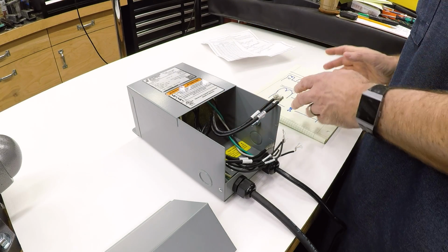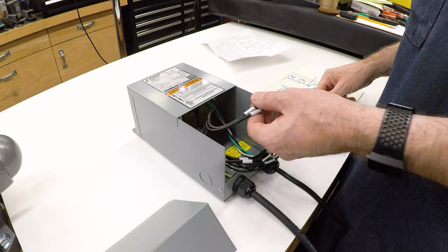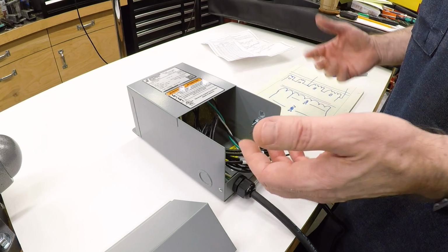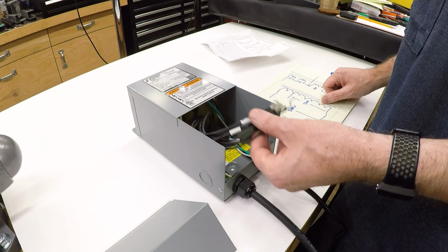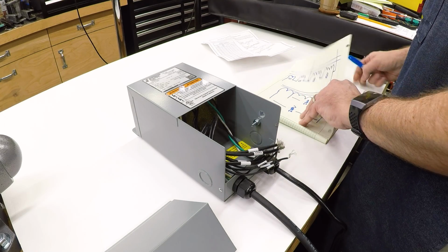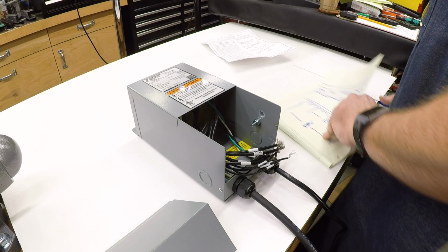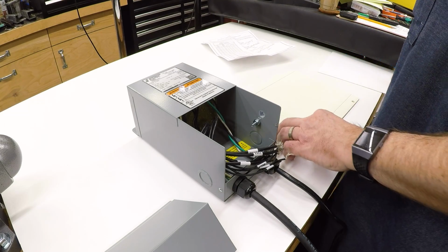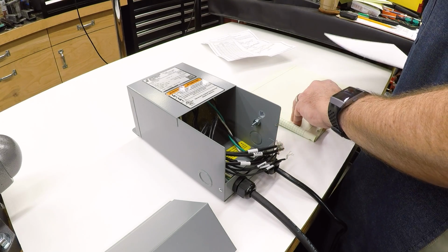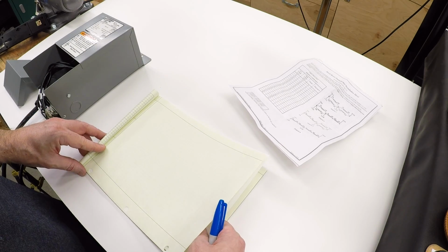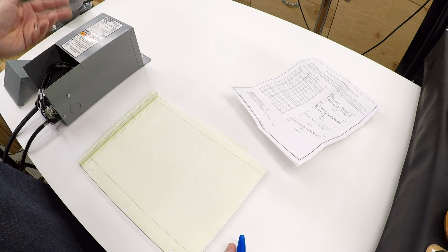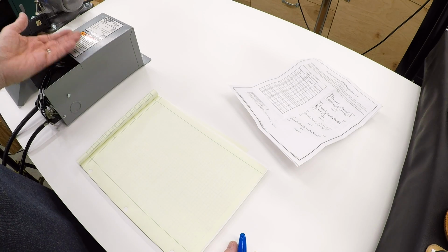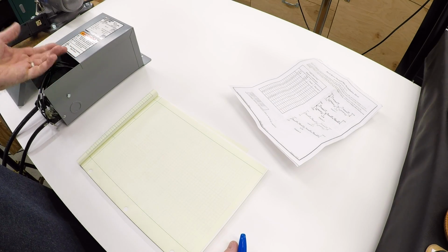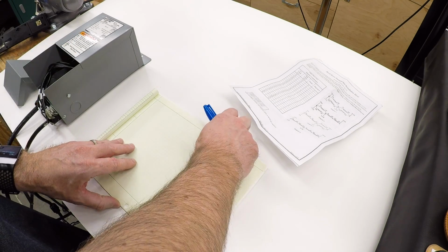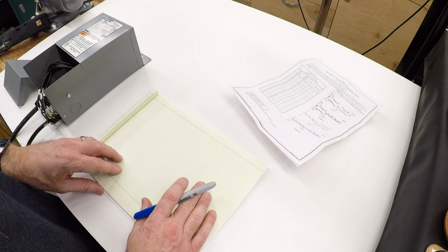But there's more to selecting a transformer than just the voltages. We also have to make sure it can handle the current, the power, or the VA that we need for our application. There are calculators online to calculate what you need and select the kind of transformer -- that's what I did to select this one, or one similar, and then locate one from a supplier I could get quickly. Let's talk a little about how transformers are sized.